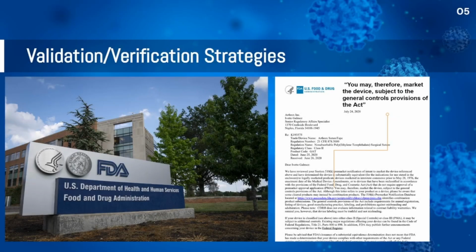After complying with regulatory authorities during the validation and verification stage, this is when a product requires clinical trials if no predicate of a device exists. One strategy that can help collect data that's necessary to test the safety and effectiveness of a device is called IDE.